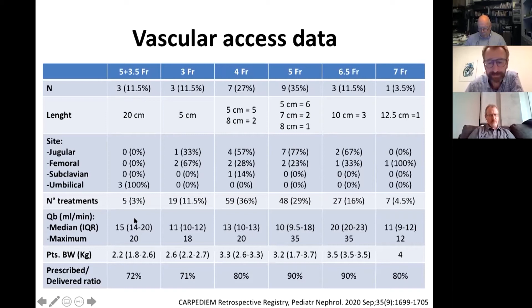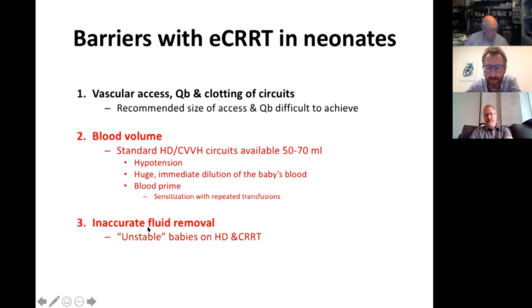So the other 2 barriers we have with the application of extracorporeal renal replacement therapy in neonates are those related to the blood volume and to the inaccuracy of the fluid removal. In this table, I've just summarized the technical characteristics of the most important monitors we have in our unit. These are adult monitors. And if you look here at the priming volumes, the priming volume with this monitor using pediatric setting is in the range between 60 and 80 ml.